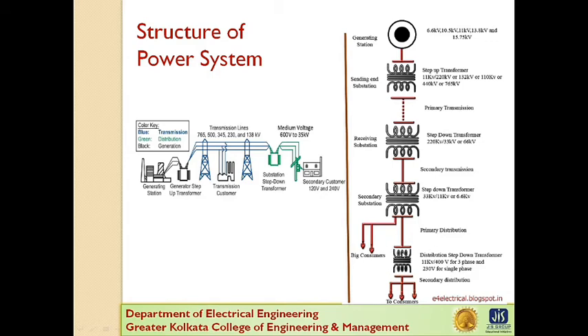distribution. The electric power from the primary distribution line at 11 kV is delivered to the distribution substation. These substations are located near the consumer localities and step down the voltage to 400 volt for three phase and 230 volt for single phase. This is for commercial uses and this is for domestic uses.